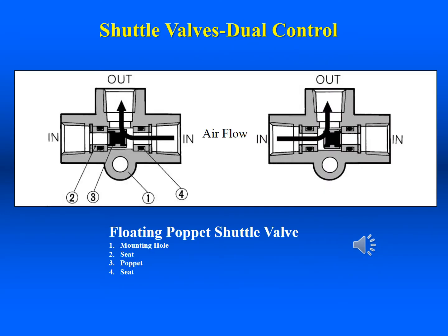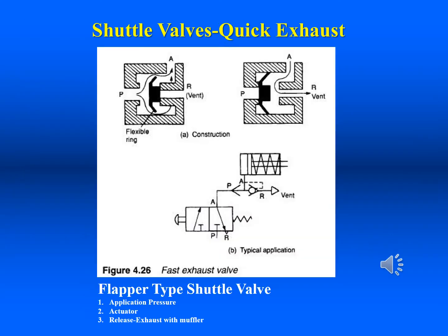Normally, check valves have only two ports. Another type of check valve can allow flow from two sources and from either source to one point. Shuttle valves have three ports. A variation of the shuttle valve is a quick exhaust valve. These three-ported shuttle valves are used to release fluid directly from an actuator to increase speed and reduce piping. They are used primarily in compressed air systems.